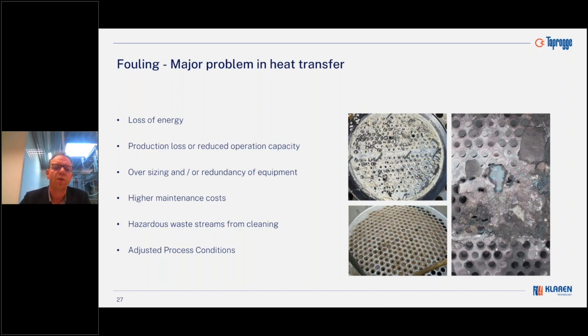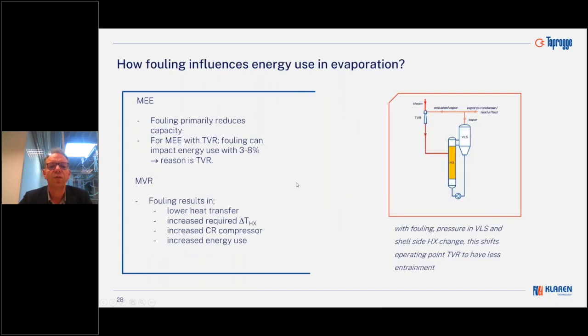And of course, if you have this, you also need to clean it, you need to look at the design. But today is about energy efficiency, so we can go to the next slide, where I will say more about how this influences, in fact, your evaporation performance. Because for a multi-effect evaporator, fouling predominantly reduces capacity. That's really the biggest issue. But in the meantime, it's also a little bit of a silent killer for your energy efficiency.